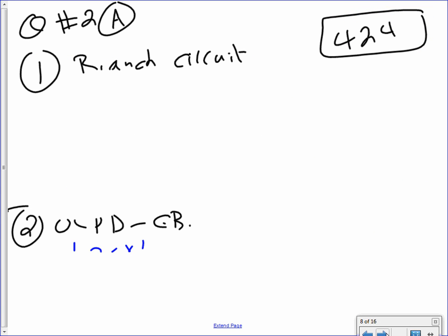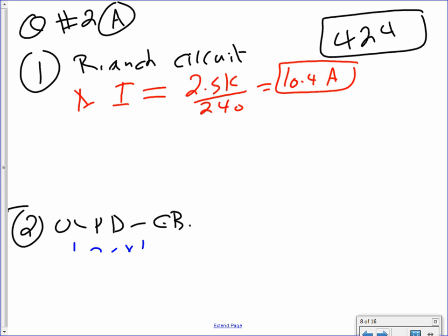Remember, they are Article 424. They are continuous load, so we are to size them as follows. The first thing you need to do, guys, is find the amps, because we size conductors and everything else based on the amps. 2.5 kW divided by 240 will get you a healthy 10.4 amps. Then you take the 1.25 and multiply this baby by 10.4. Why 1.25? Continuous load, 424 tells you if it's continuous load, add 25% extra when you size your conductor. That will give me 13 amps.